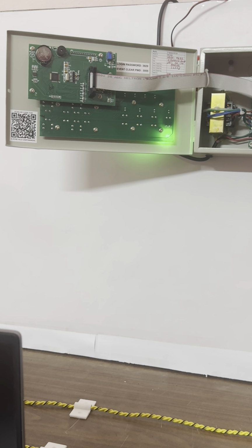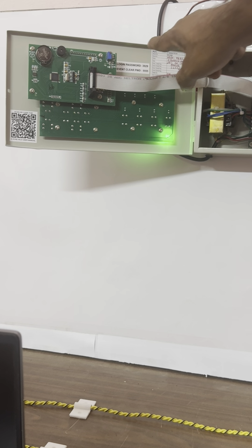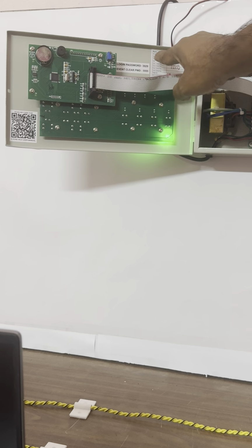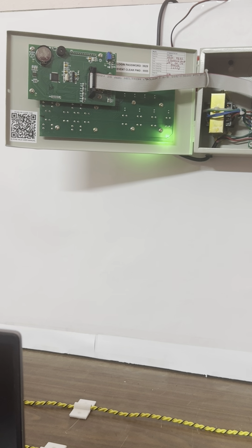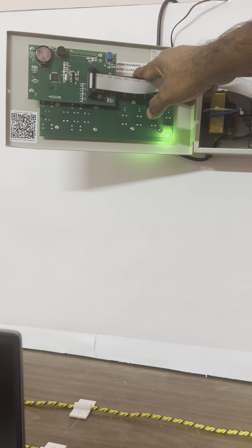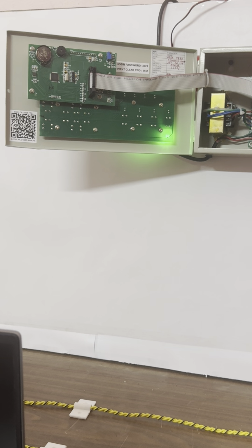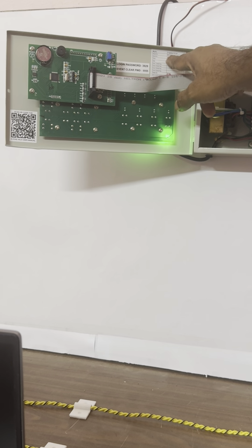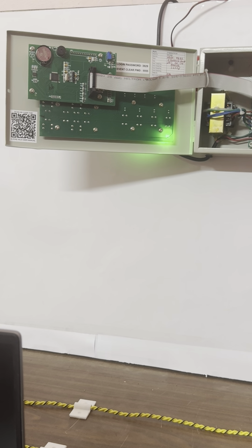On the back side of the front door, you will be able to see a QR code, a sticker for the password, and a nameplate sticker. When you scan this QR code, you will be able to download the user manual for this particular product. This is the login password and event log clear password, which is printed on the back side of the panel, and there is a panel serial number with the date, and zone enabling serial keys are provided in the sticker. So now I am going to start the configuration part.